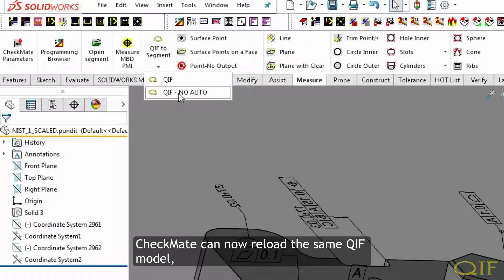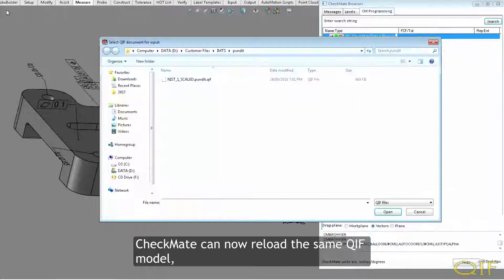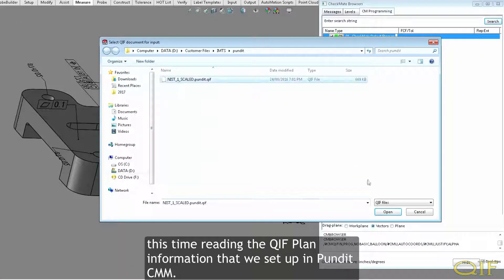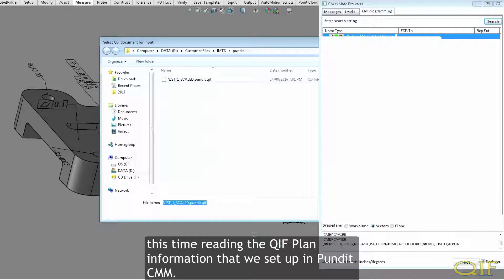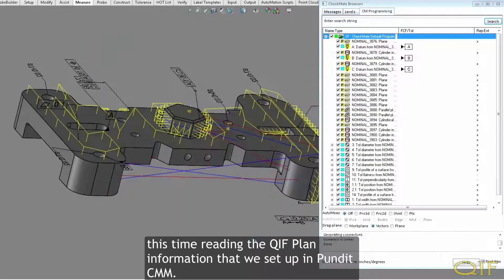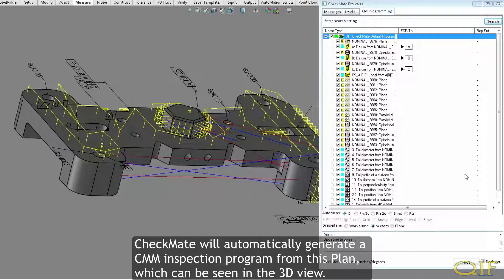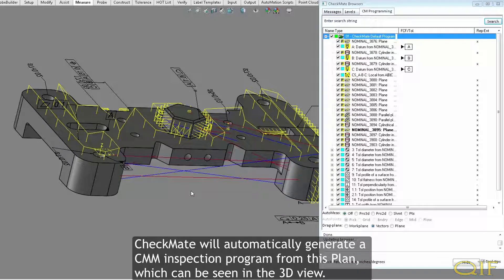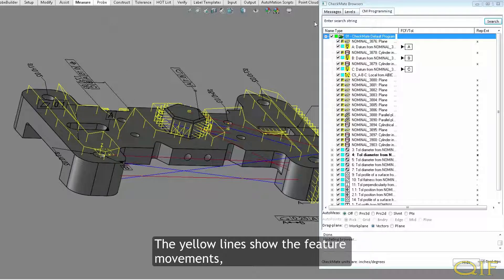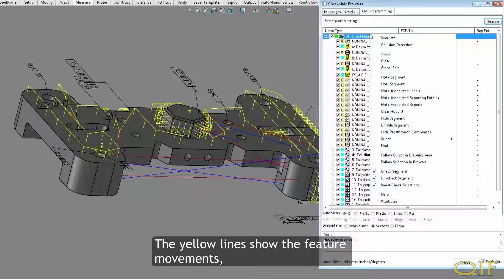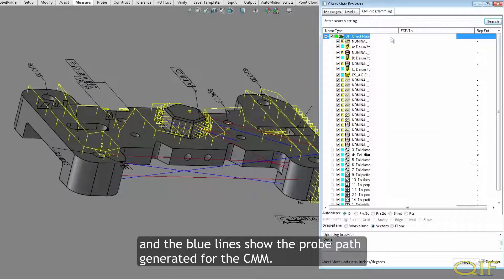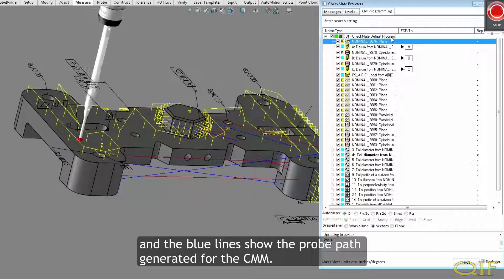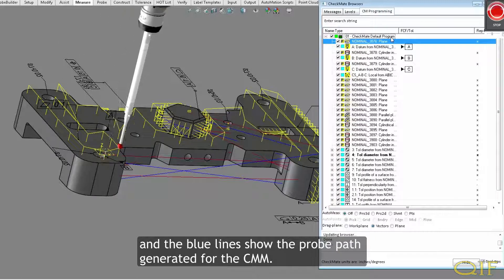Checkmate can now reload the same QIF model, this time reading the QIF plan information that we set up in PunditCMM. Checkmate will automatically generate a CMM inspection program from this plan, which can be seen in the 3D view. The yellow lines show the feature movements, and the blue lines show the probe path generated for the CMM.